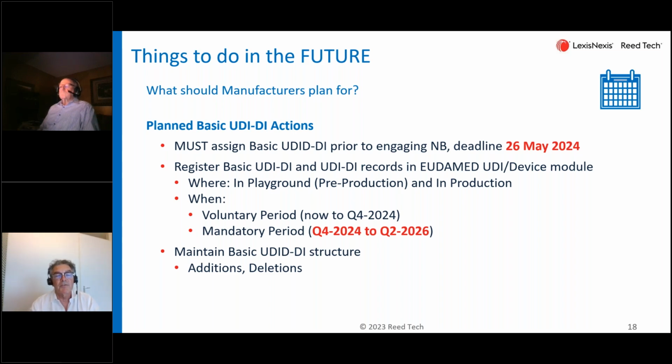Okay, enough about that. If you have set up your basic UDI structure, at the moment you become certified under the MDR, you must use UDI in all your records. So then you can start registering it in EUDAMED. Until then, if you're not an MDR device or IVDR device, there's no need to register in EUDAMED. Once you're certified, you can start entering.